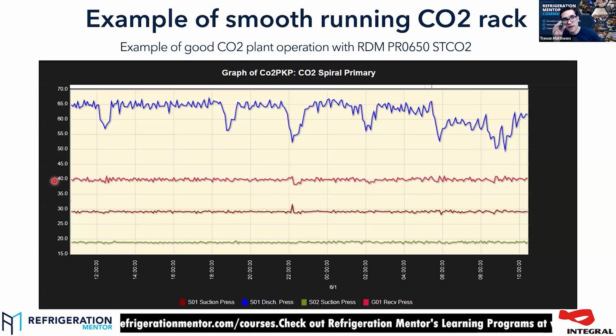But like you said, it's when the system starts to change its load. They load up, they leave a door open, a fan goes out, whatever. And that's when the dynamics happen. And to get it like this, though, it doesn't happen. You don't just start up a system. This is another thing with case controllers. You don't just put it in and all of a sudden it's going to work. No. And it depends on the nature of your load.